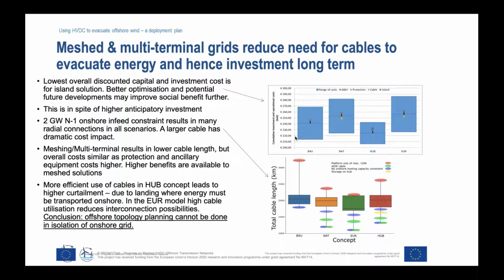We've used the 2 gigawatt N-1 onshore infeed constraint, which results in many point-to-point connections in all the scenarios. A larger cable would have a dramatic cost impact. What we also see is meshing and multi-terminal results in a much lower cable length, but the overall costs end up being similar as protection and ancillary equipment costs are higher, and especially the substructure costs to carry those.